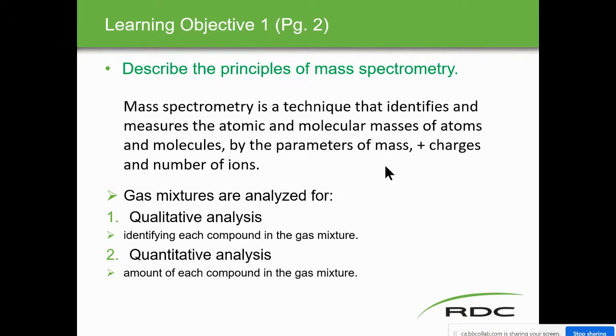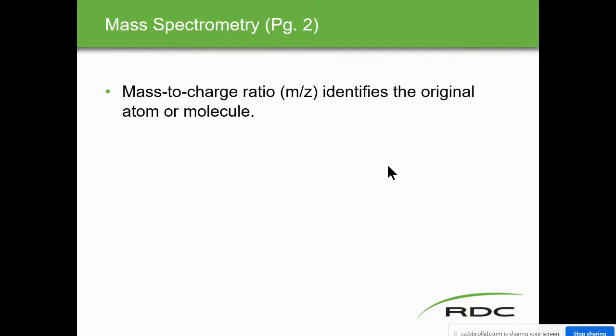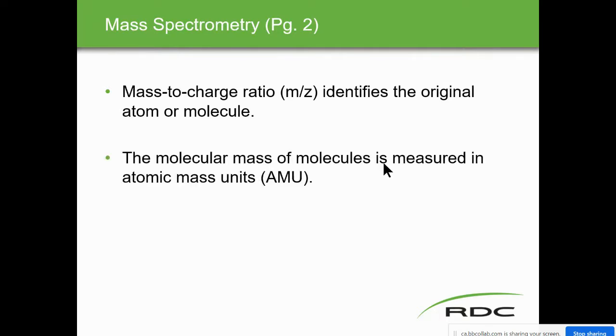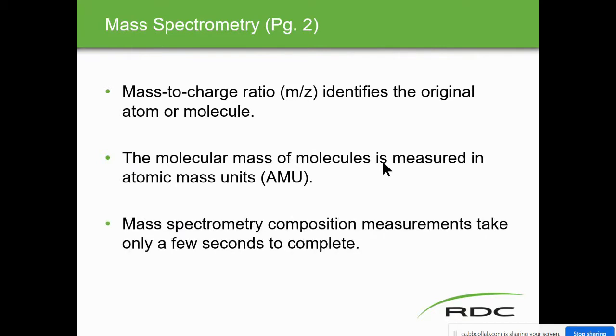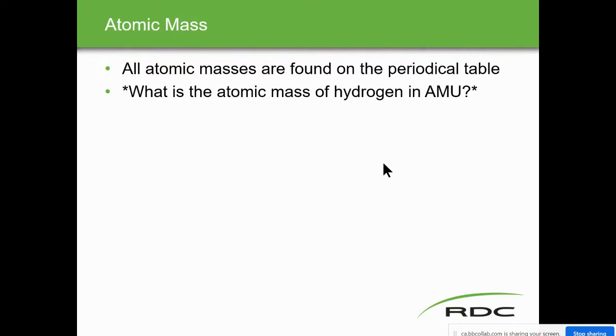All of these atoms, elements, and molecules are found on the periodic table, and each one has a molecular mass. These analyzers separate and identify against known compounds, elements, and molecules. They also measure the positive charges of the number of ions — every molecule going through the analyzer is made into a positive ion. They are gas mixture analyzers only, performing qualitative analysis — identifying each compound in the gas mixture — and quantitative analysis, measuring the amount of each compound.